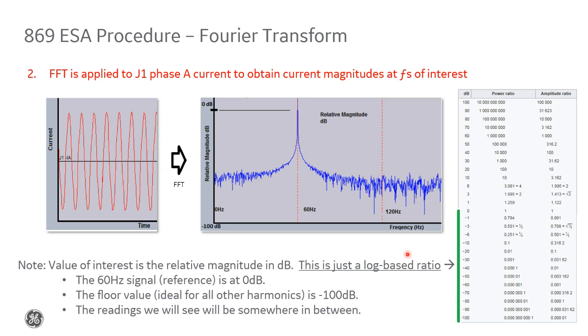So the second step we do is the fast Fourier transform of the A phase current signal to put it into the frequency domain so that we can see the full spectrum of frequencies that make up the signal. If you're not familiar with looking at the frequency domain, the decibel unit for the magnitude of the frequencies can be a little bit confusing. What the decibel is looking at is just a log-based ratio, which provides a number line compression scale so that we can graph a large data variation together. We show this in the table that you see to the right here.